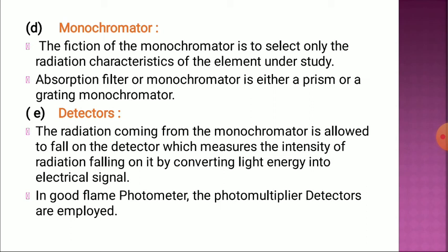As a detector, we can also use a photomultiplier detector, or we can say a photocell. Okay, these two types of detectors are employed in the flame photometer. Okay, these are actually the components of the flame photometer.